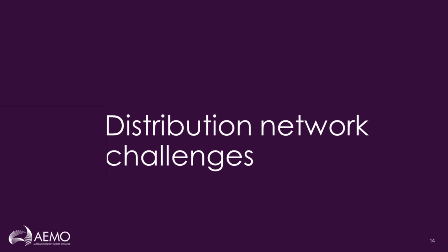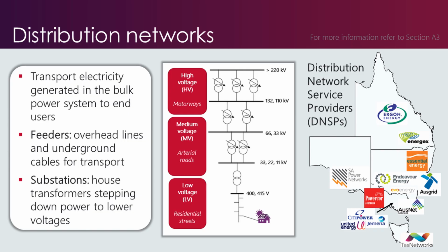electricity market? Distribution networks are the poles and wires historically designed to transport electricity generated in the bulk system down to end users. They consist of substations and feeder paths successively stepping electricity down for efficient and safe reticulation. This journey is summarized in the middle panel you can see here. The vertical lines represent overhead lines or underground cables. The horizontal lines represent a given voltage level. We've marked here typical voltage levels at each point here in Australia. And the symbol with the two overlapping circles is a transformer, which converts voltages between levels and sits within substations.